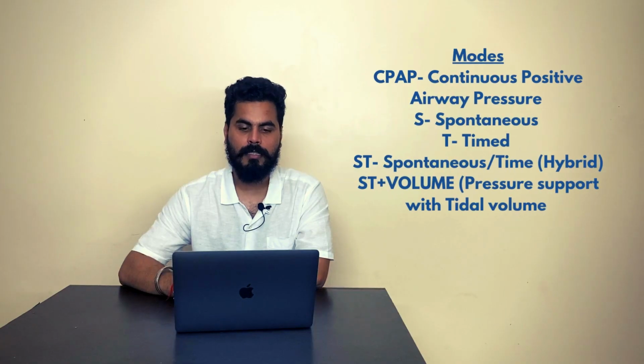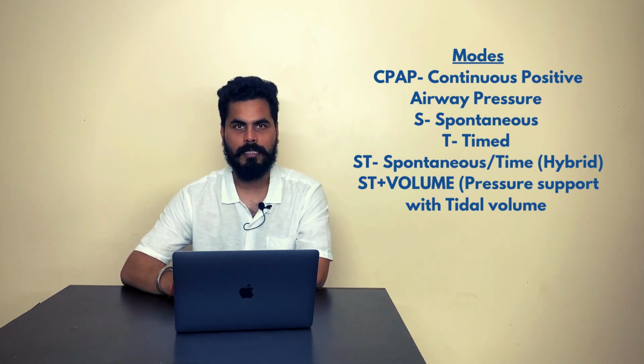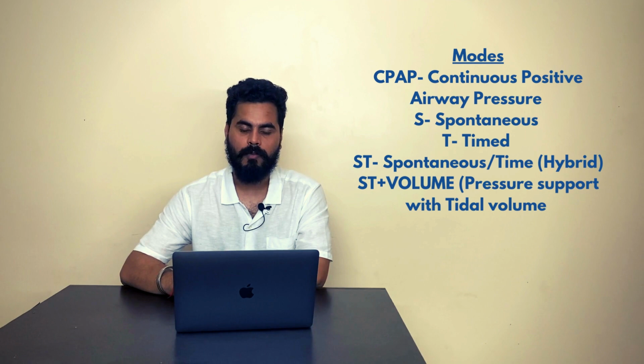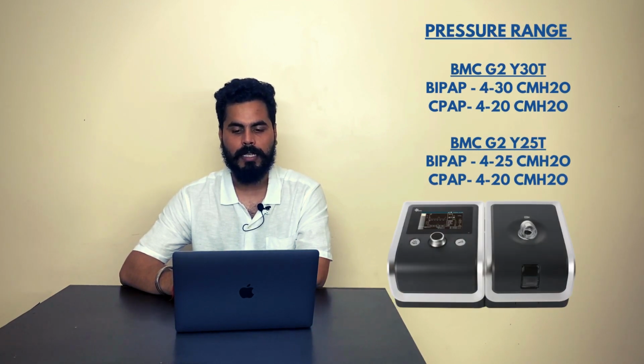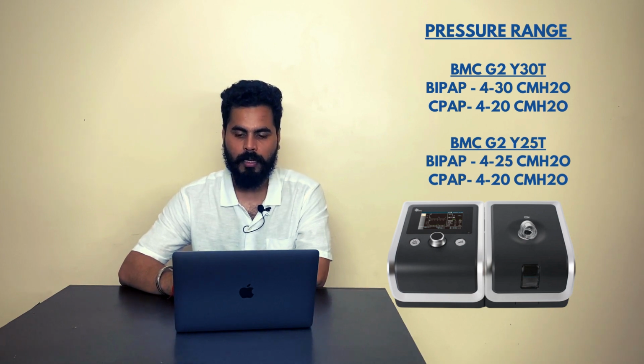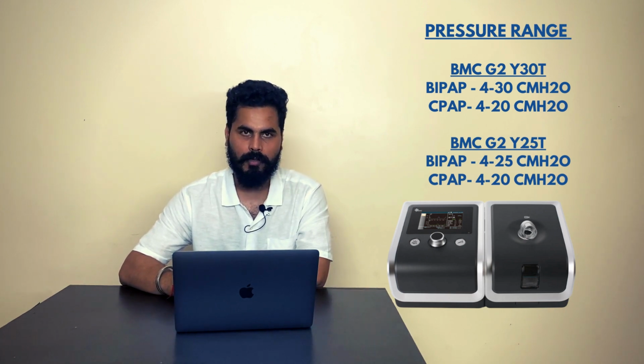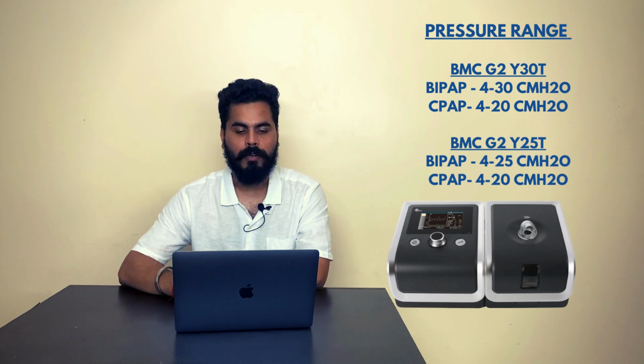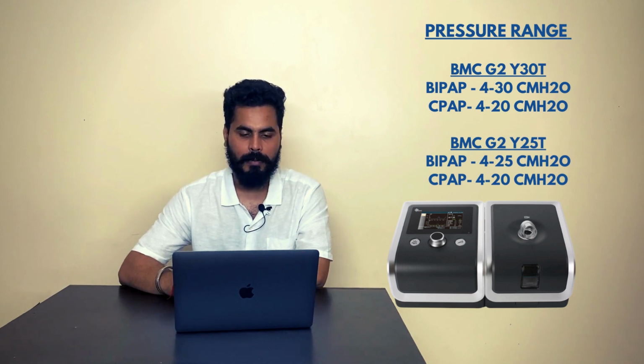Now let's discuss the clinical features of this model. There are 5 major modes available in this device. One is CPAP, one is S, then T, ST, and ST with volume guarantee. Pressure range in the Y30 model is 4 to 30 cm of water in BiPAP mode, and 4 to 20 cm of water in CPAP mode. In the Y25T, 4 to 25 cm of water pressure range is available in BiPAP modes, and 4 to 20 cm of water in CPAP mode.